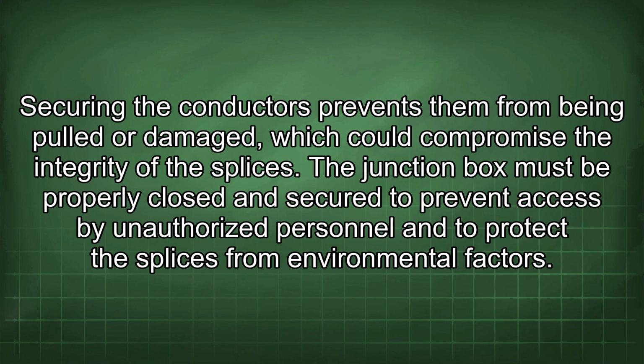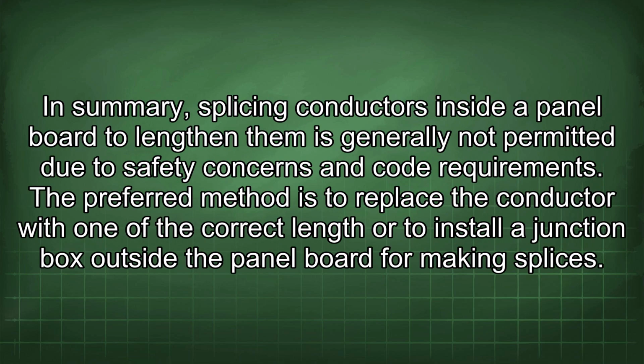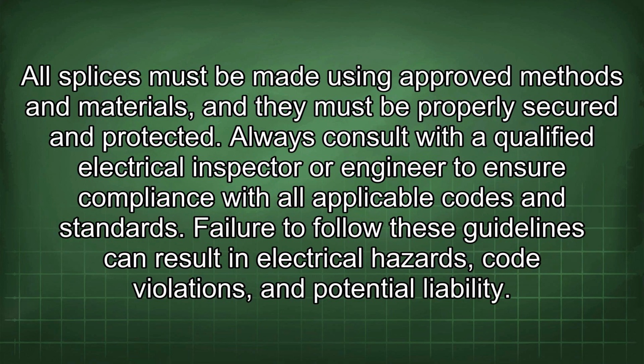from environmental factors. In summary, splicing conductors inside a panel board to lengthen them is generally not permitted due to safety concerns and code requirements. The preferred method is to replace the conductor with one of the correct length or to install a junction box outside the panel board for making splices. All splices must be made using approved methods and materials, and they must be properly secured and protected.